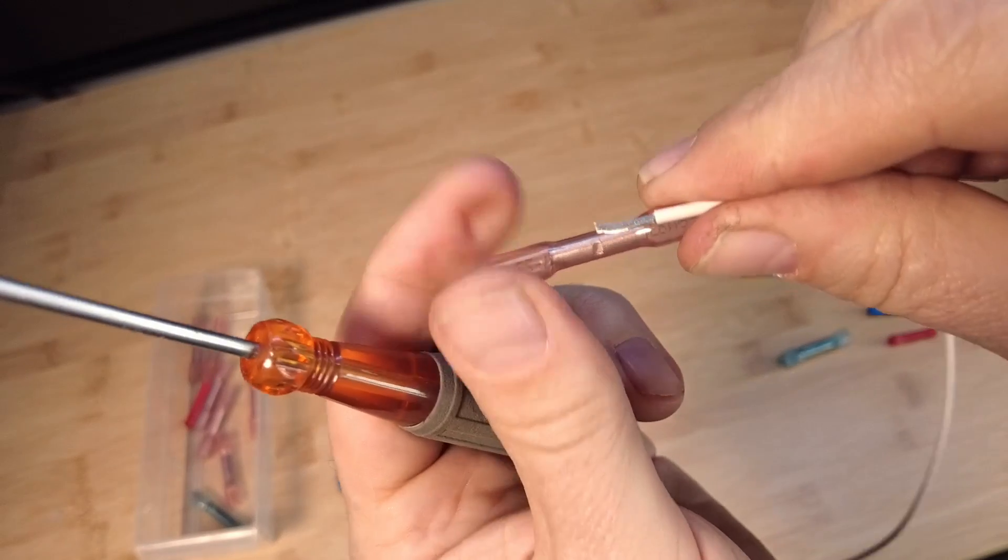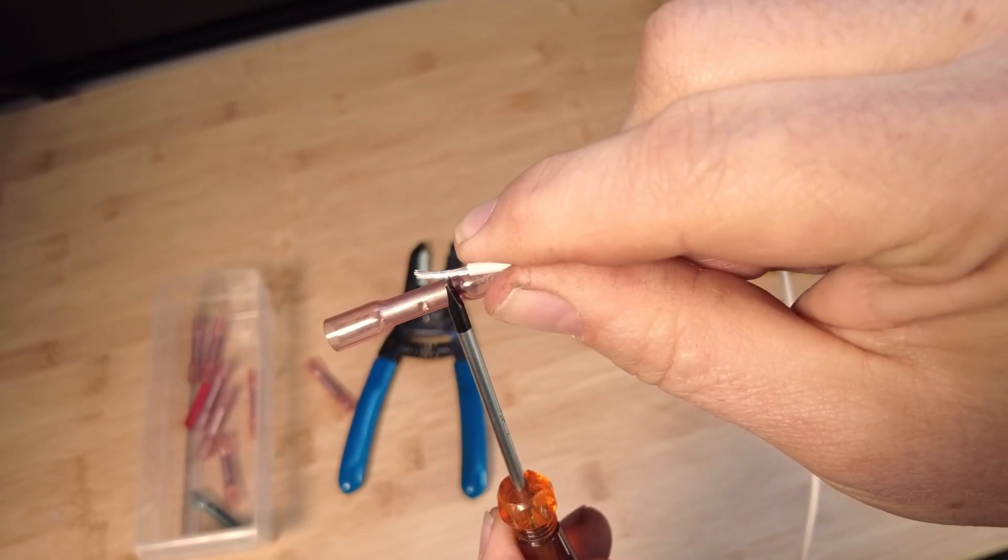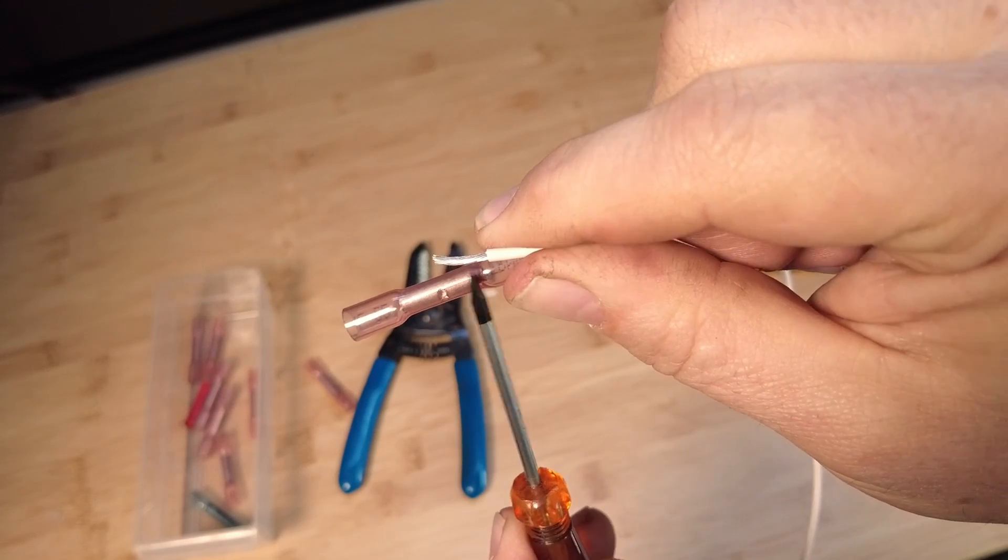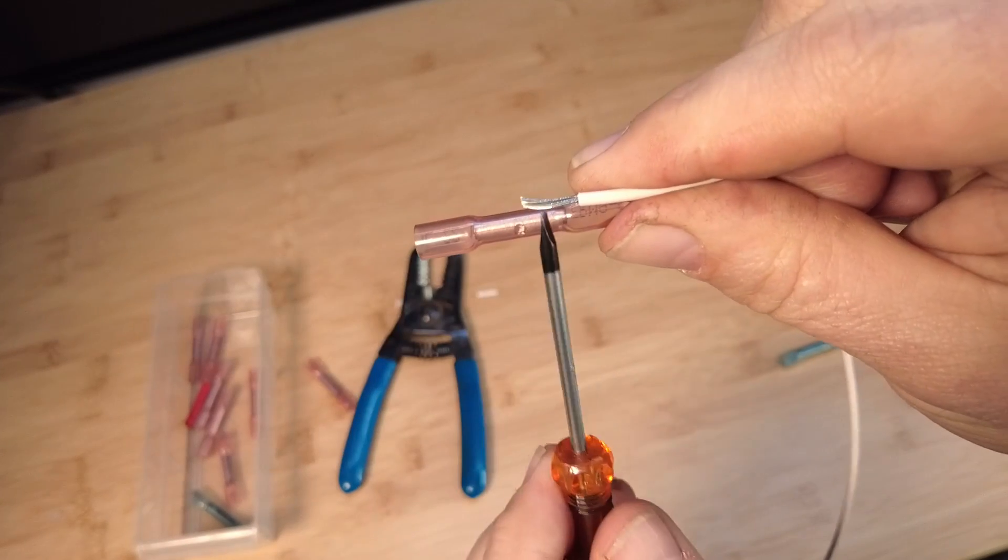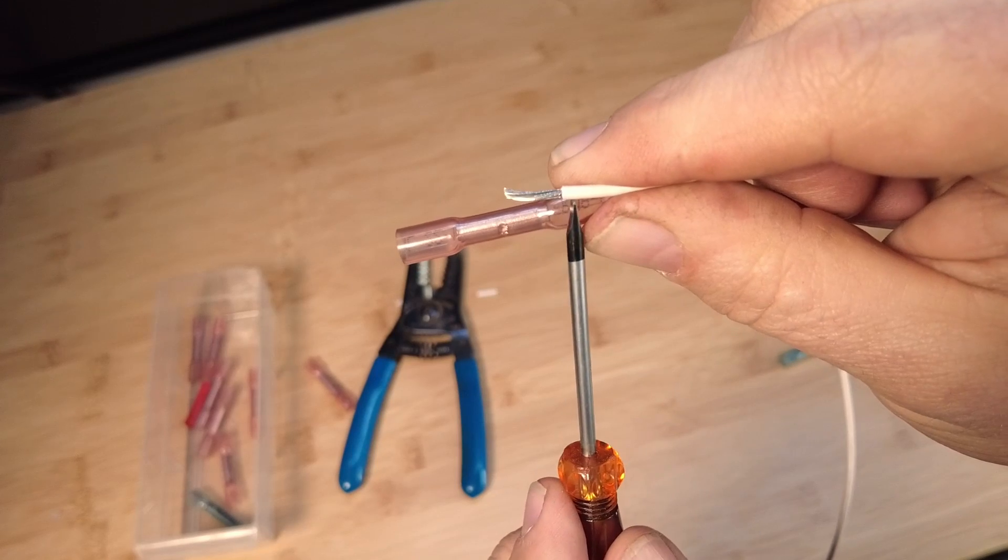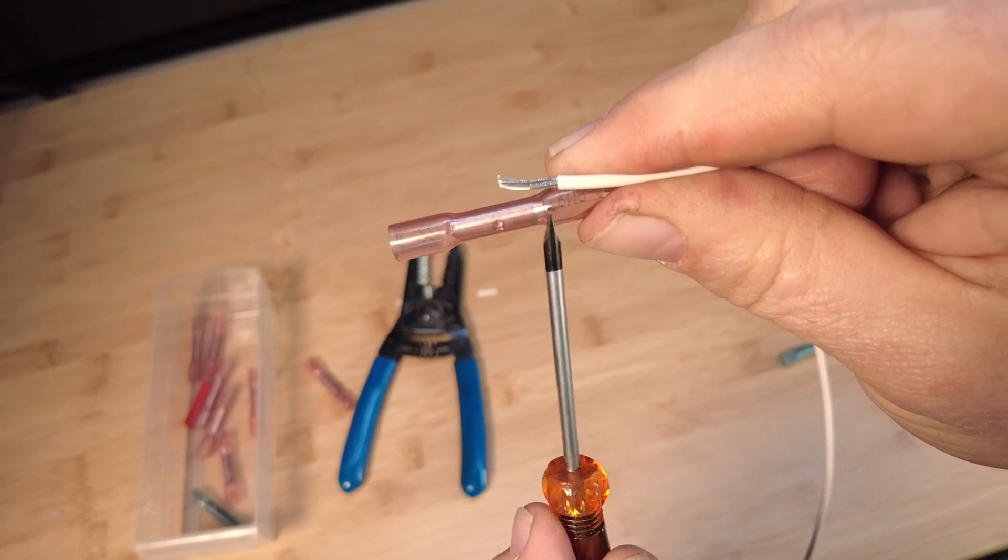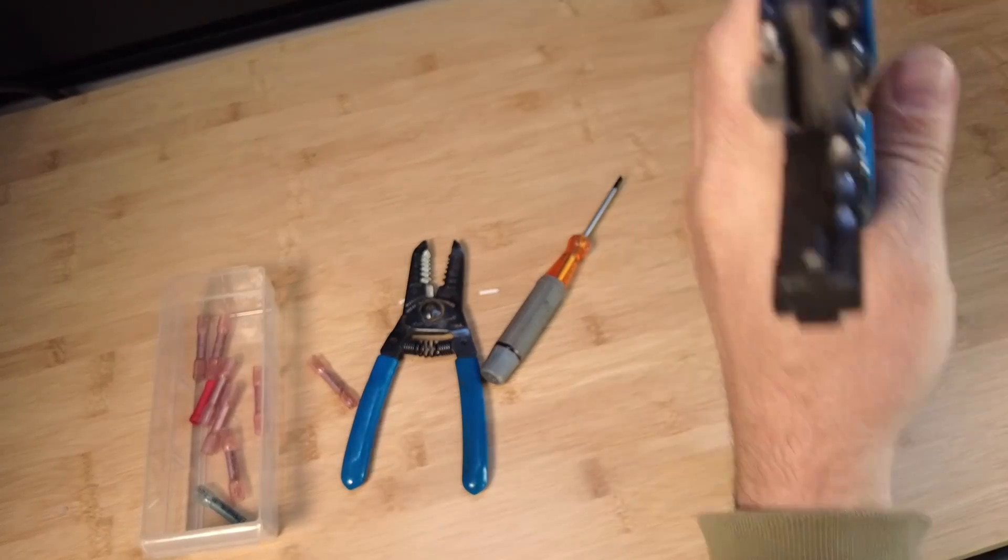then you run the risk of crimping on the insulation rather than on the copper. So I'd rather have a little bit more. You can always cut this off shorter too, but I'd rather have this stripped back a little bit more because it's still going to be well hidden under the heat shrink jacket.